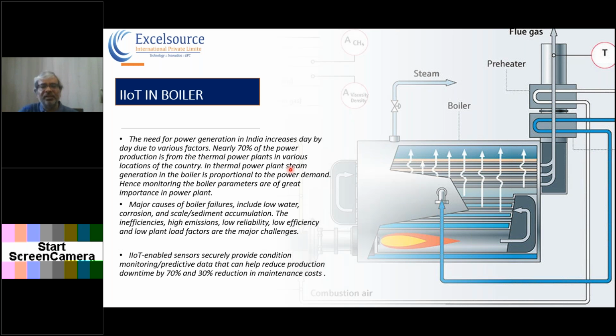So if all three heat recoveries and the combustion efficiency in the boiler are maintained, it is going to operate at a certain efficiency. To keep monitoring this, whether fouling is happening within the furnaces, the economizer, the air preheater, or the water preheater, various sensors at various locations have to be installed, and data monitoring has to be done. Take into consideration the efficiency of the instrument. What I am going to say about the efficiency of the instrument is not exactly the efficiency, but the least count of the instrument which is installed.